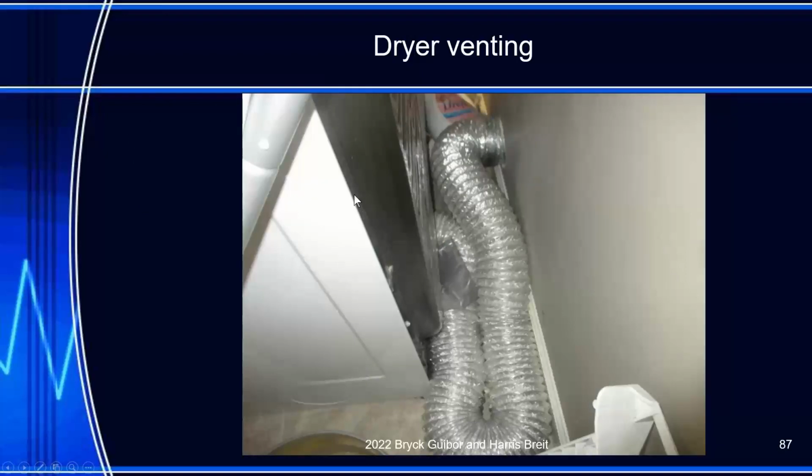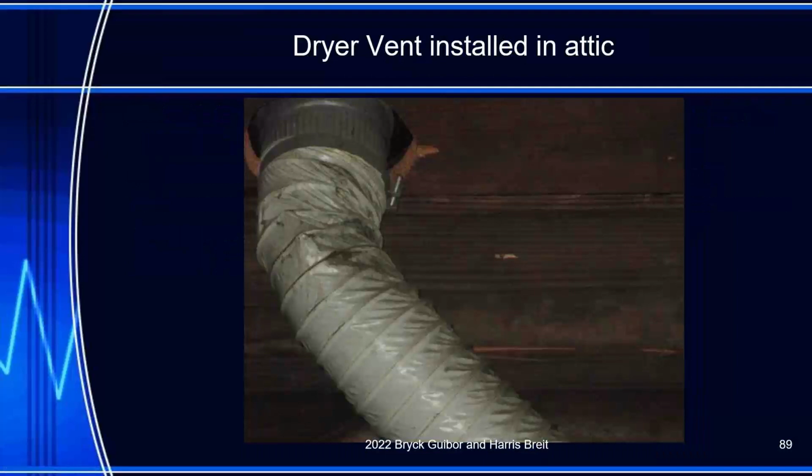This is gas. So is this flex line okay for gas? It's got too many bends. Yeah, it's got a lot of bends in it, first of all. So that's my first issue. And then I'm going to have to look at the box and see if this is rated for a gas dryer. Too many bends.